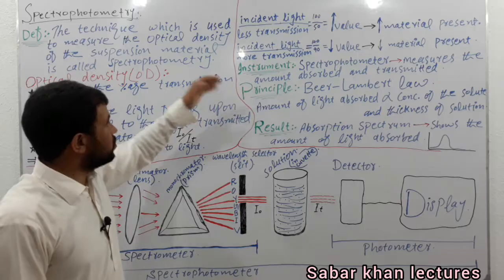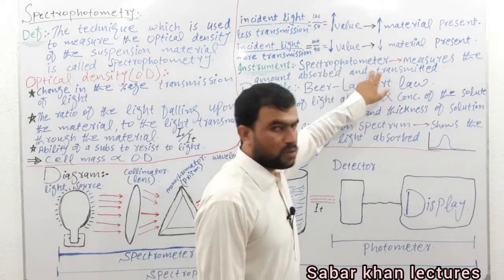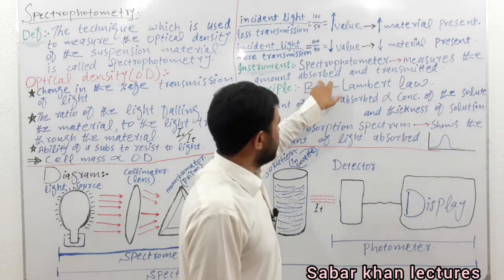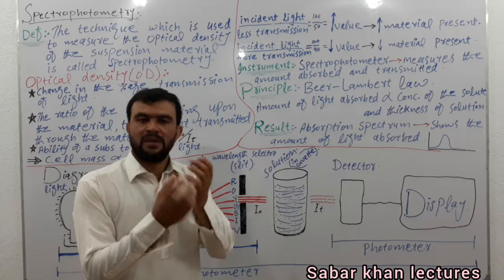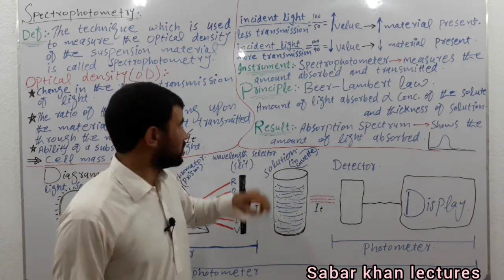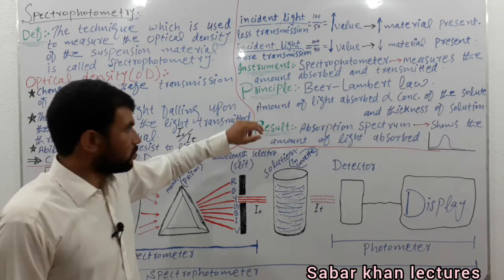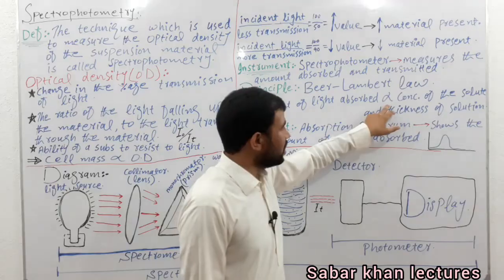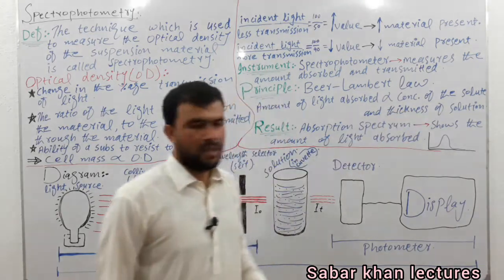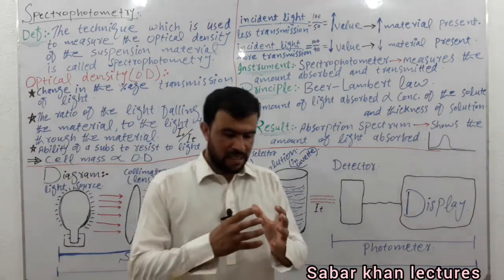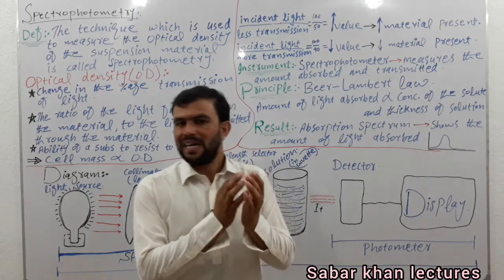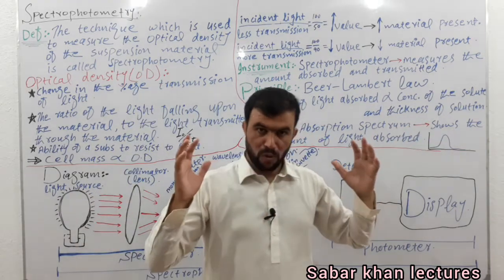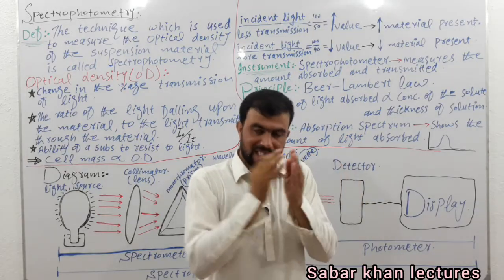Now we will come towards the instrument used in spectrophotometry: the spectrophotometer is used. It measures the amount of light absorbed and the amount of light transmitted. The principle used in spectrophotometry is Beer-Lambert's law, which states that the amount of light absorbed is directly proportional to the concentration of solute and the thickness of the solution. When solute concentration is more, more light will be absorbed; when less, less light will be absorbed. Similarly, when solution thickness is more, more light is absorbed; when less, less light is absorbed.